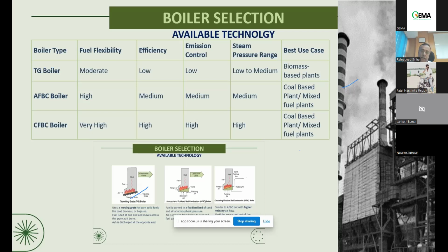And it is basically best used for the coal-based plant, and where you are going for a mixed fuel plant, where you can have say a 50-50 mix between the coal and the biomass, or 60% 40%, and where you are looking for flexibility of fuel. You are not sure. Obviously nobody is sure from where exactly the fuel will come tomorrow. In that case, the AFBC boiler is very suitable. Similarly, CFBC boiler, and obviously there is a capital cost difference between the TG boiler and AFBC boiler. AFBC boiler is slightly costlier than TG boiler.